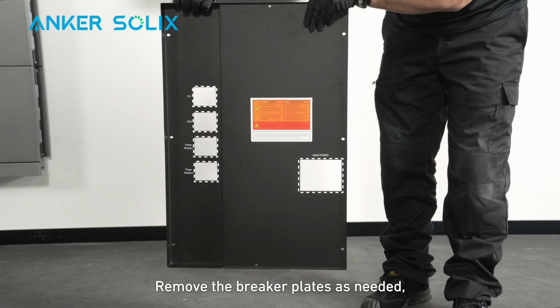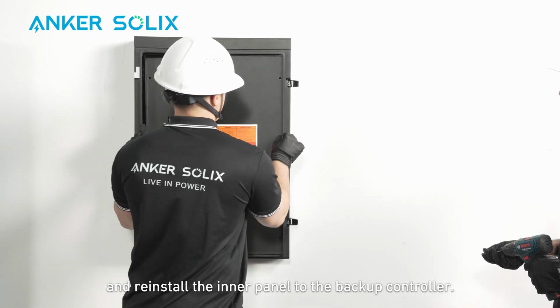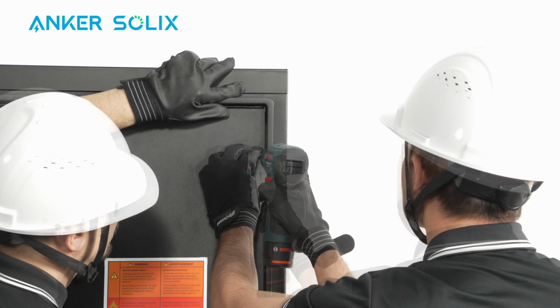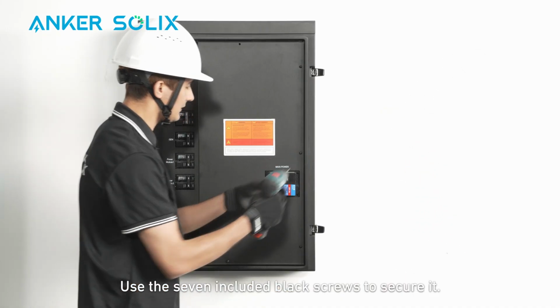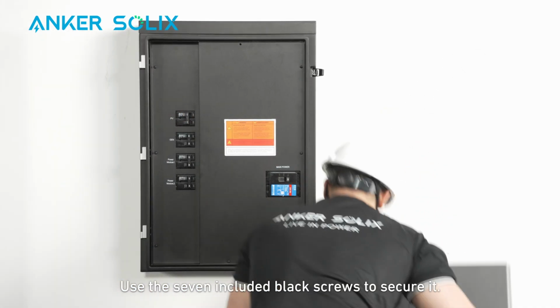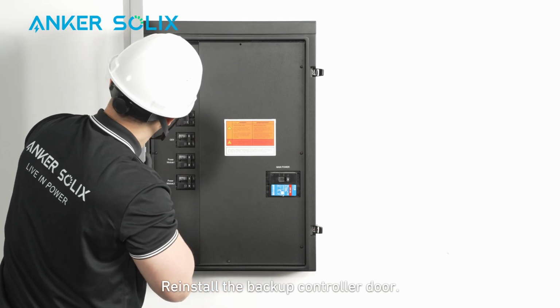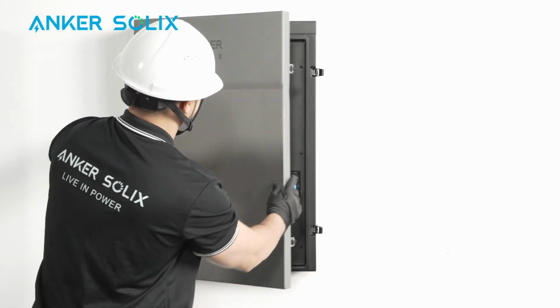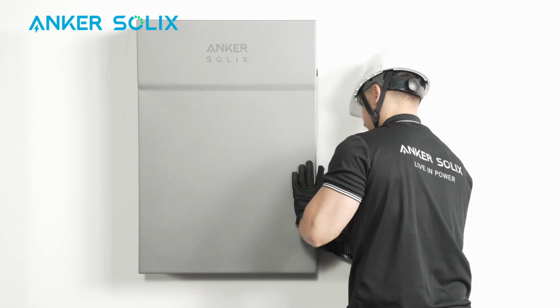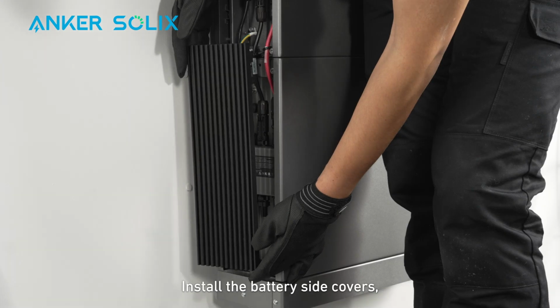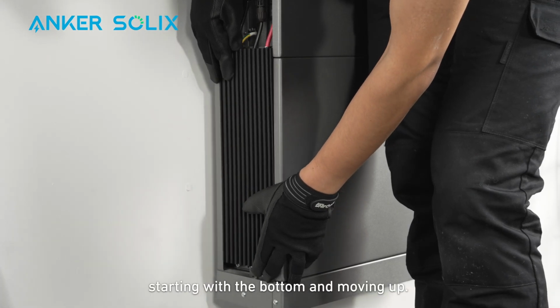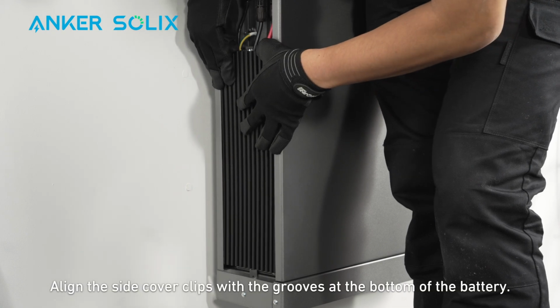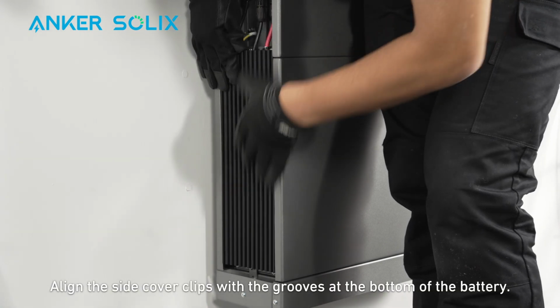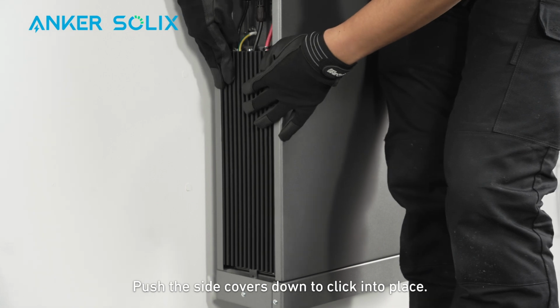Remove the breaker plates as needed and reinstall the inner panel to the backup controller. Use the 7 included black screws to secure it. Reinstall the backup controller door. Install the battery side covers, starting with the bottom and moving up. Align the side cover clips with the grooves at the bottom of the battery. Push the side covers down to click into place.